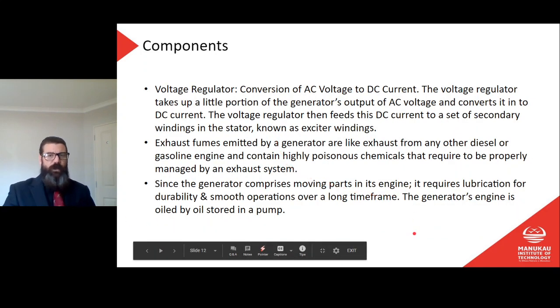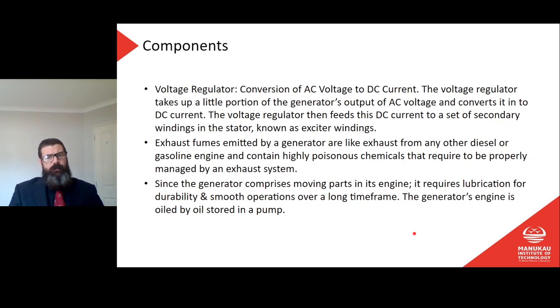Voltage regulator, the conversion of AC voltage to DC current. The voltage regulator takes up a little portion of the generator's output of AC voltage and converts it into a DC current. The voltage regulator feeds this DC current to a set of secondary windings in the stator known as the exciter windings. It does lots more than that.